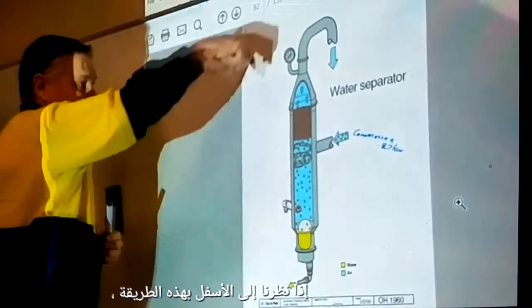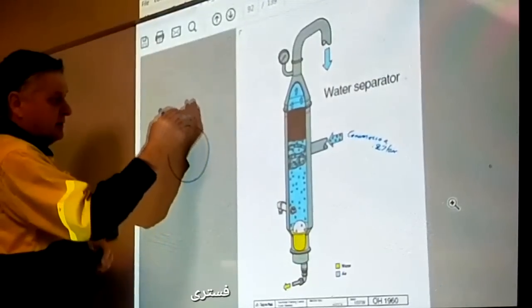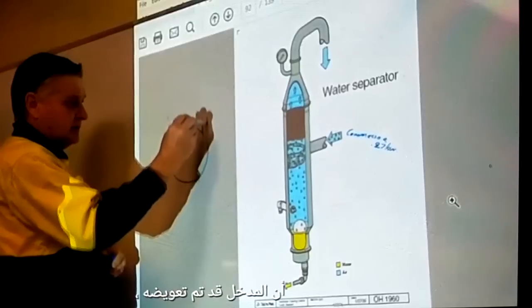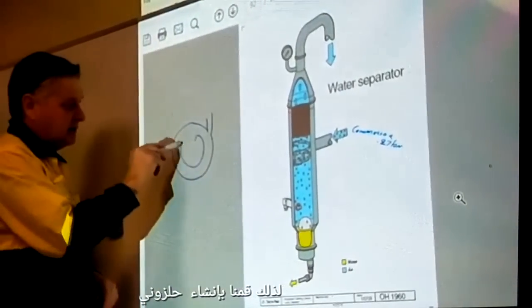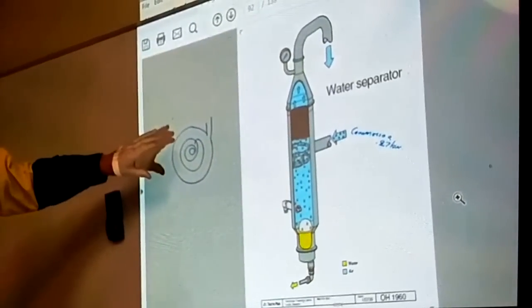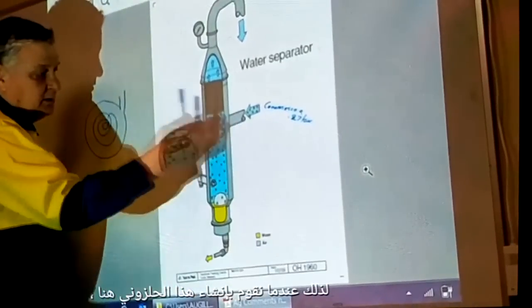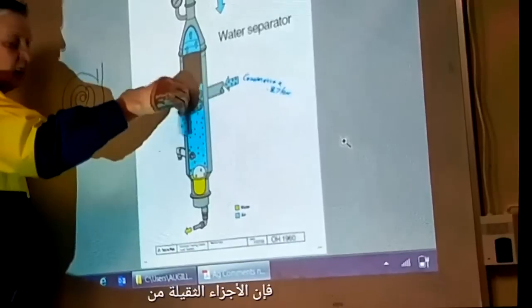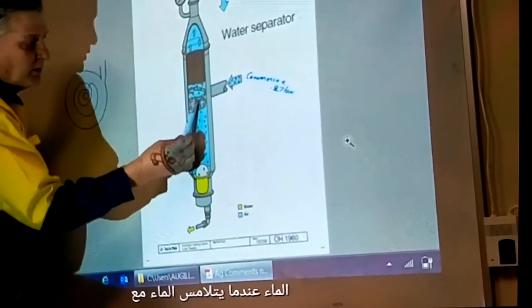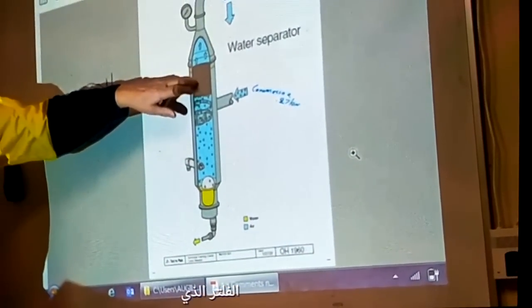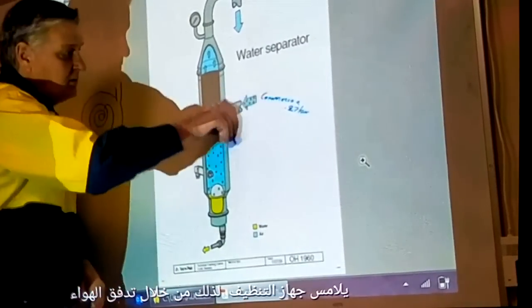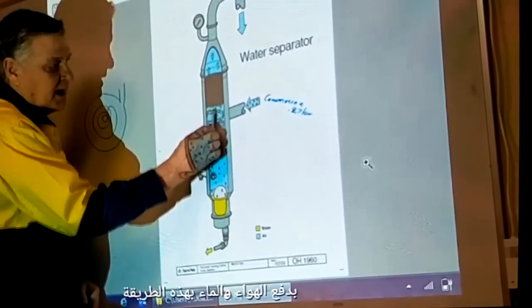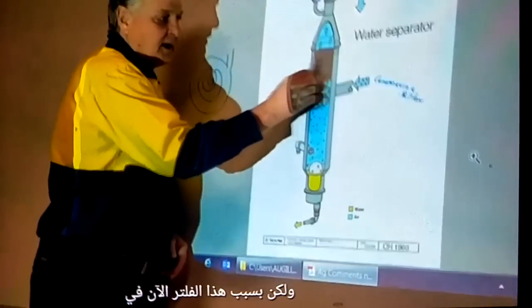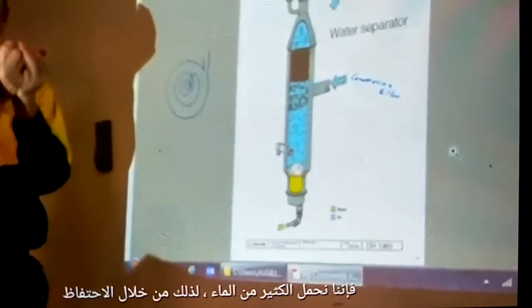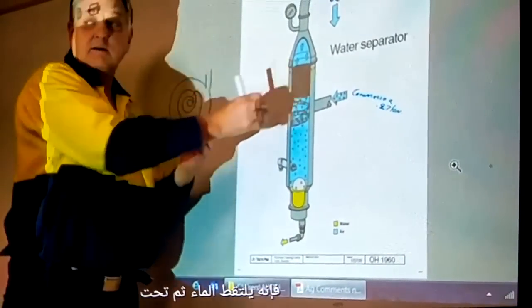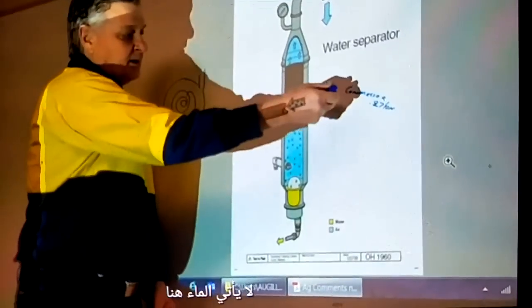If we look down this way, you will see the inlet is offset. So we create a spiral with air and water inside the water separator. When we create this spiral, the heavy parts of the air-water mixture, the water, will fall down when the water gets in contact with the filter. This is the same filter that's in the scrubber. By the airflow and the spiral action, we push air and water this way. Because of the surface area, the filter holds a lot of water, and then under the weight of the water, it falls down.